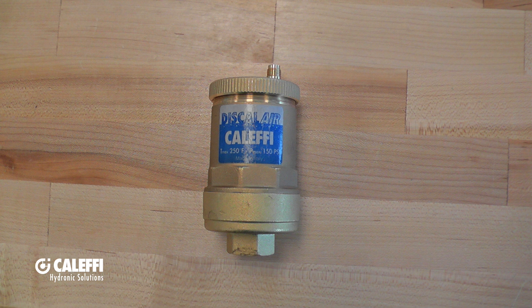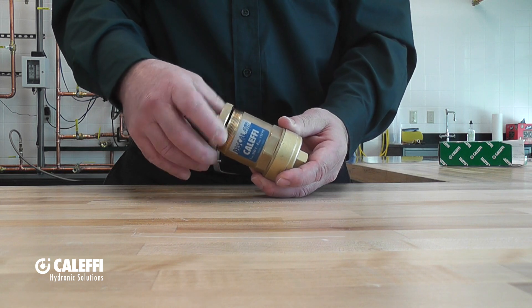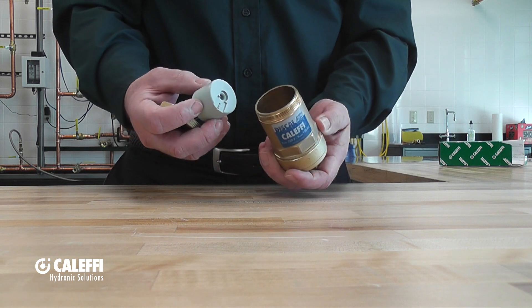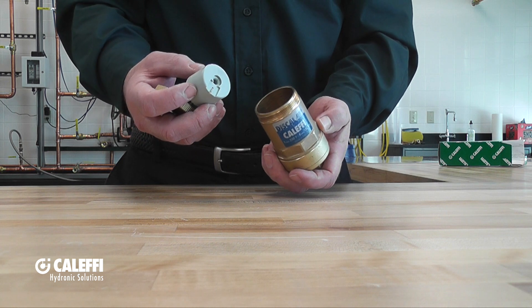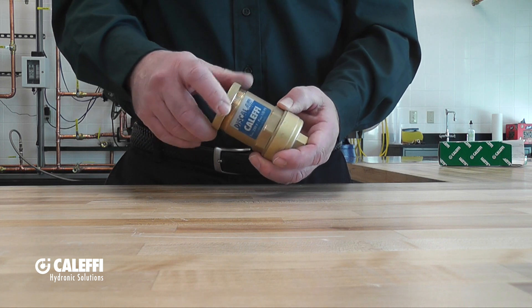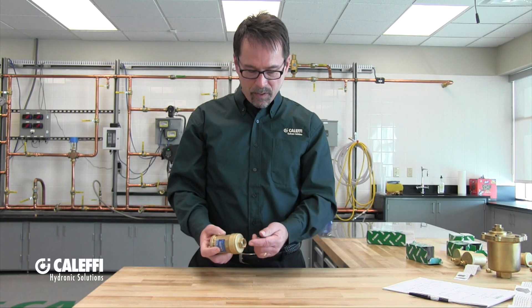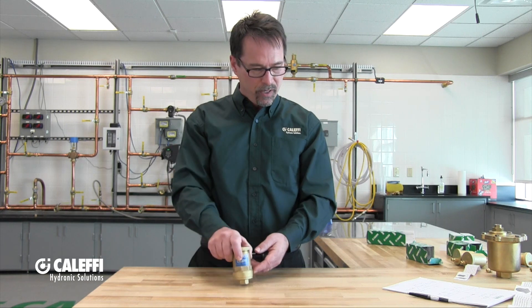Let's talk about the 551 Discal Air. This is a high-capacity, high-performance air vent, and what makes it special is the pin-guided float. That makes it perfect for installations where the vent may not be perfectly vertical. The inside is repairable — in fact, it's replaceable. You can order a whole new internal. It has a female NPT connection, and it will pass 1.8 to 3 SCFM.